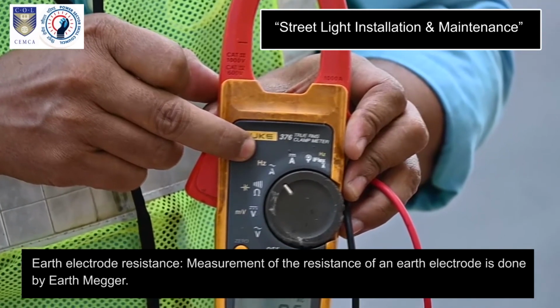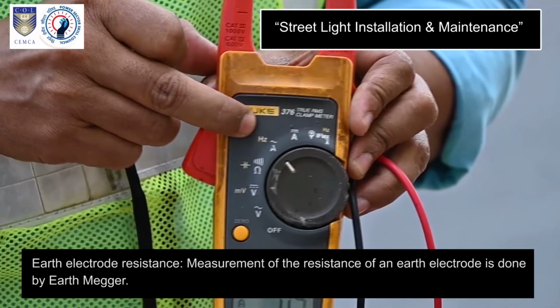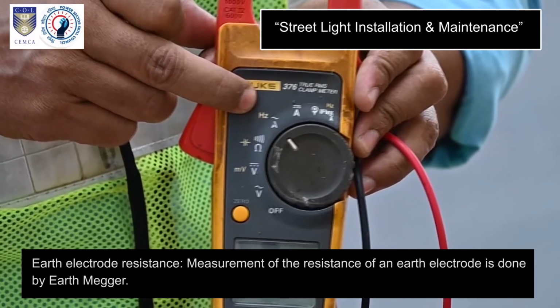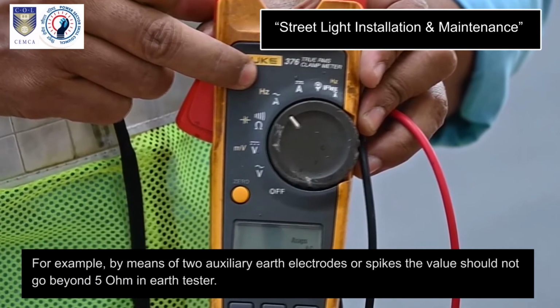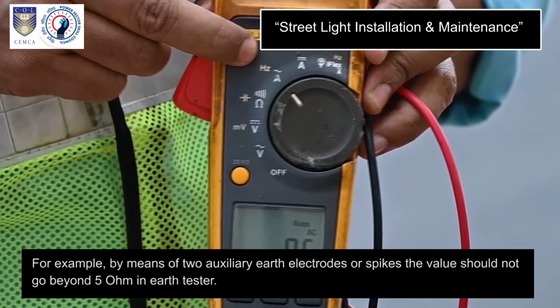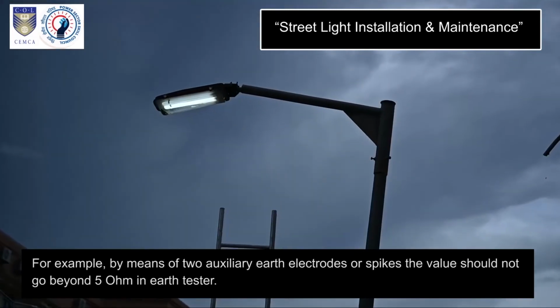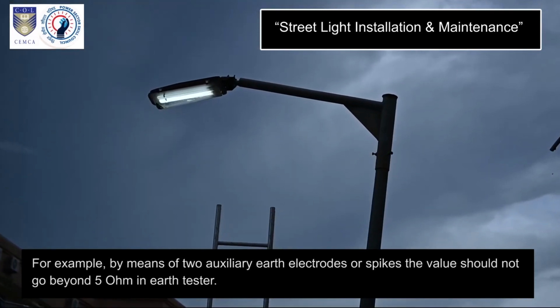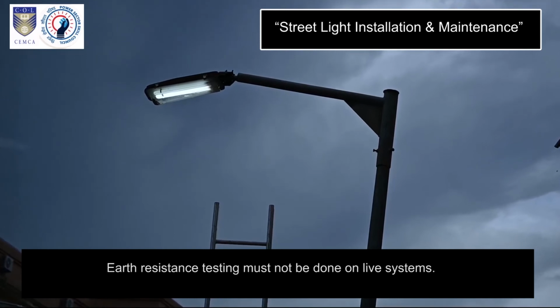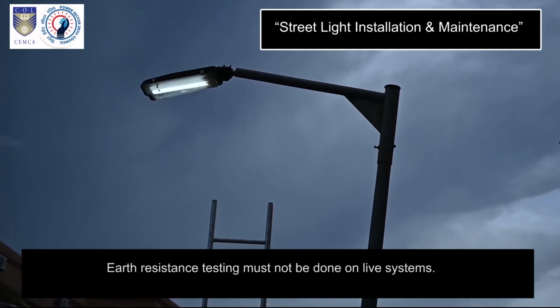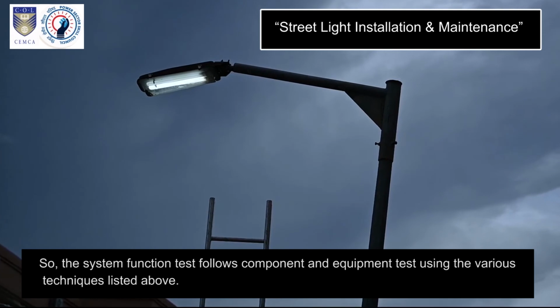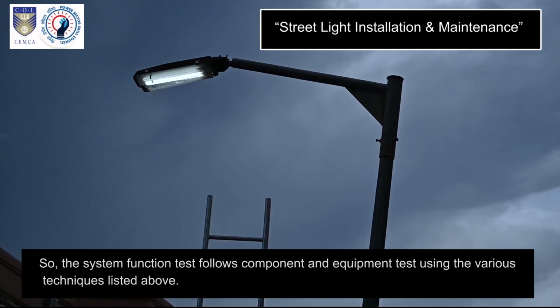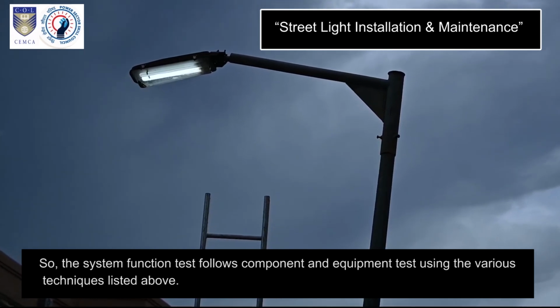Earth electrode resistance. Measurement of the resistance of an earth electrode is done by Earth Megger, for example, by means of 2 auxiliary earth electrodes or spikes. The value should not go beyond 5 ohm in the earth tester. Earth resistance testing must not be done on a live system. So the system function test follows component and equipment tests using the various techniques listed above.